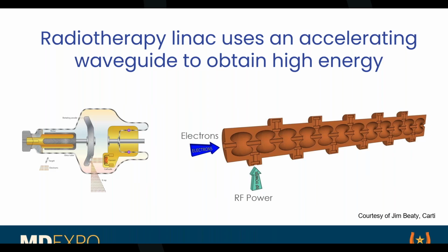And so there was a progression of the technology. In an X-ray tube, we have a rotating anode, a kind of direct acceleration tube. You can get 100 kV. That's not difficult with the kind of transformers we have today. And in a single transformer device, you can probably get to about 500 kV pretty easily without things getting too big and too complicated. But that's about as high as you can go. People have tried. In the 1930s, GE came up with a tube that had a 1 MeV potential on it, and it was just a big, massive thing.